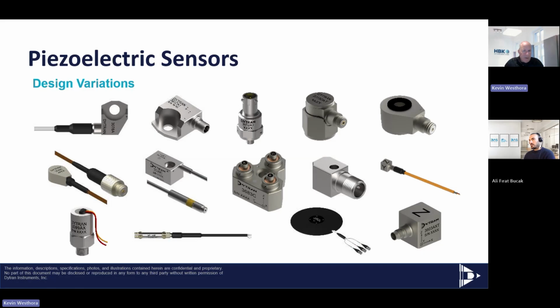And so the upper frequency is very limited with that accelerometer because of the size, the mass, and the connector, which make the upper limit frequency very rough, very difficult to measure. That accelerometer probably has a natural frequency of about 70 kilohertz, but a usable frequency of probably 3 kilohertz maximum. Versus this sensor way over here, this little teardrop has probably a natural frequency of about 100 kilohertz and a usable frequency over 10 kilohertz. So the upper frequency of an accelerometer is dictated by the design of the sensor, the connector, the mass, the weight.